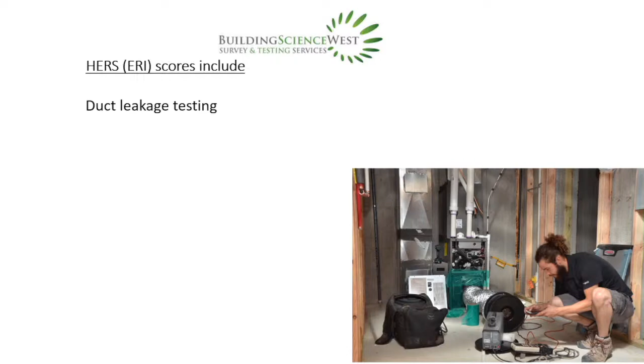There are different rings you can put on the fan to change its accuracy—if you've got a system that leaks very little, you'll use a ring that necks it down for more accuracy. The little gray box in front, which I'm sure we just used for the photo, is a theatrical smoke machine. Those really only get used for presentations, or when you've got a leaky duct system and you're trying to prove to HVAC contractors that their systems actually leak. You blow smoke into it, they see it ooze out through all the joints, and then they actually believe their systems leak.